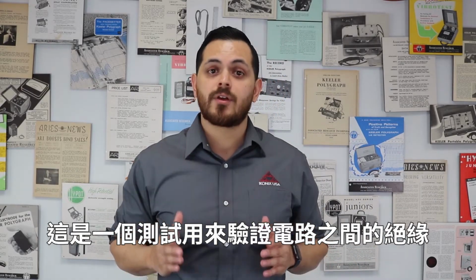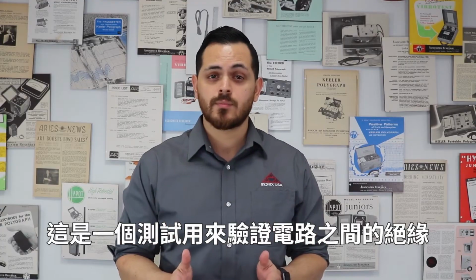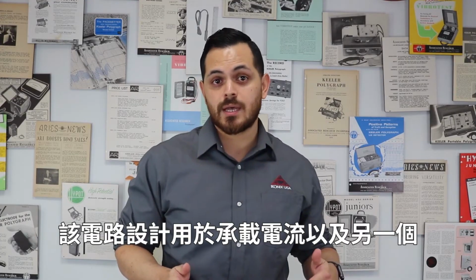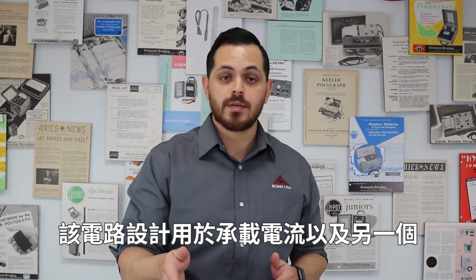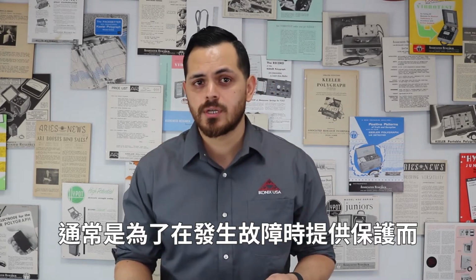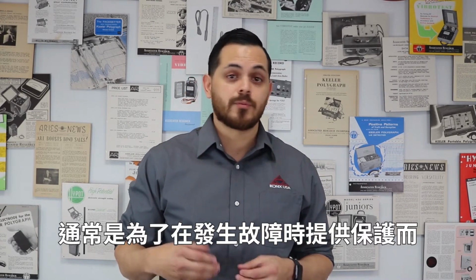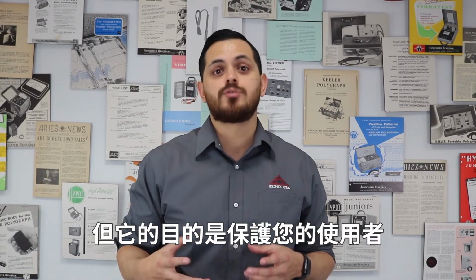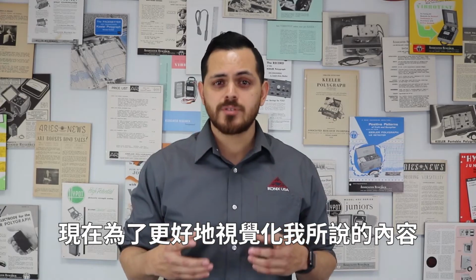It's a test to verify the integrity of the insulation between a circuit which was designed to carry current and a different circuit, usually the ground circuit, which was designed for protection in case there's a fault, but it's there to protect your user. Now, for a better visualization of what I'm referring to, let's go to our board and get a clearer picture of what's happening during a Hipot test.